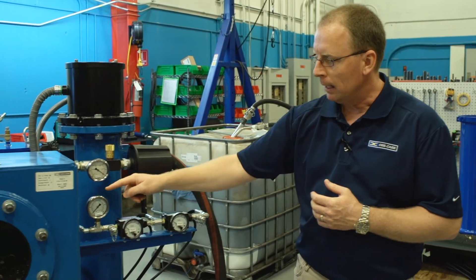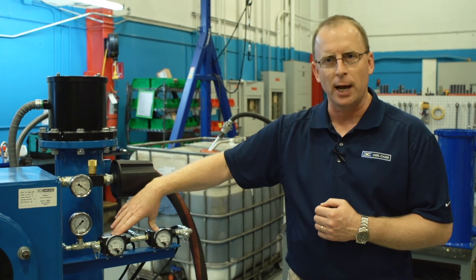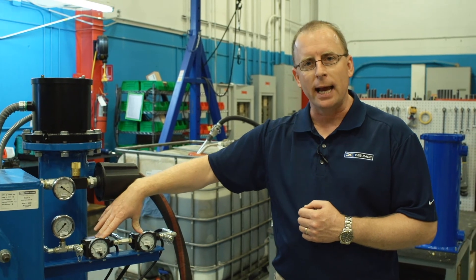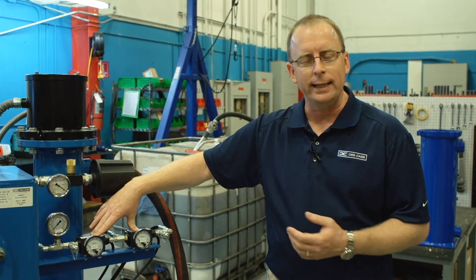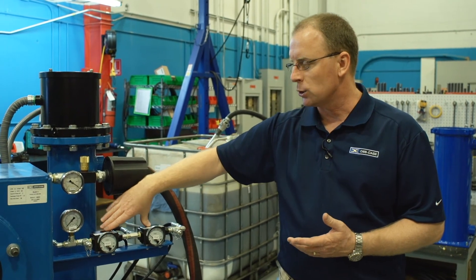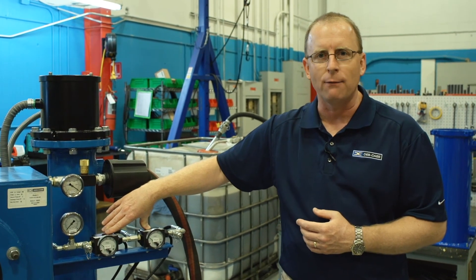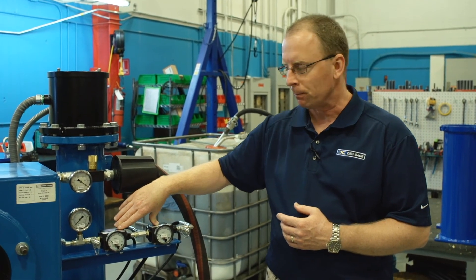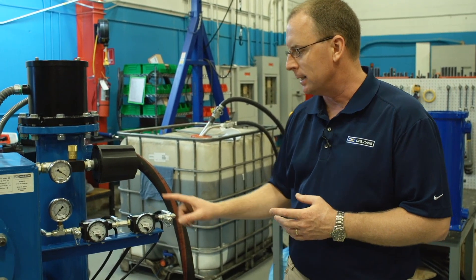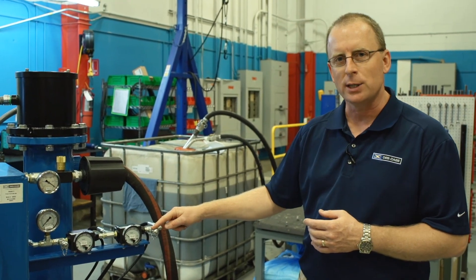Down below we have the discharge pump pressure gauge and the filter change indicator gauges, or pressure differential gauges. These indicate to the operator when the discharge filters need to be changed. They also include switches on the back that will activate an alarm on the control panel at 40 PSI differential. Also included standard on all Des-Case VAC systems are sample ports — a pre-filter and a post-filter sample port.